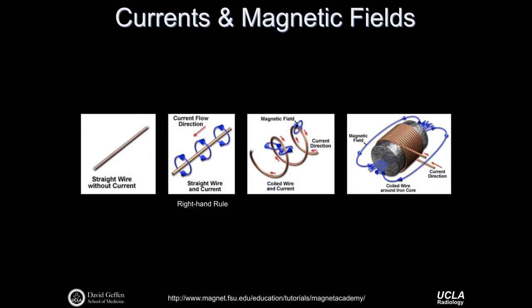The main magnetic field is actually generated using wire carrying current. A straight wire with current forms a magnetic field according to the right-hand rule. Bending that wire into a coil or solenoid generates very high magnetic fields on the inside and relatively low fields elsewhere. A conventional electromagnet may add an iron core to further concentrate field lines, but in an MRI scanner we can't use an iron core because we need to leave the bore open for patients and other objects being imaged.